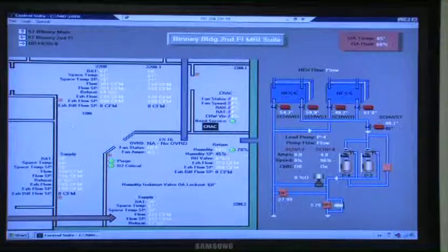How that laid out. One of the things I want to make sure of, when you look at this, is that each one of these penetrations has a waveguide. Anything that goes through has a waveguide. Those waveguards have access to them to be cleaned. Remember we talked about that? So what we'll end up doing is, when you see these penetrations come through, Jamie, can you put a little tiny label called waveguide, so people understand there are waveguards in there.